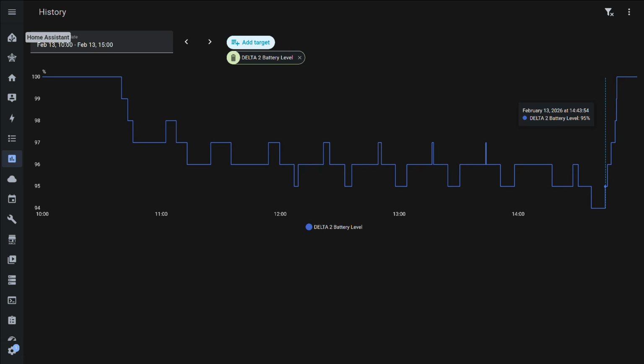By the way, this scheme, in case of not very long outages, will allow keeping the station's main battery in a gentler mode, for example charging up to 80% and discharging to 20%, essentially operating only at the expense of the external battery, which is much easier and cheaper to replace.